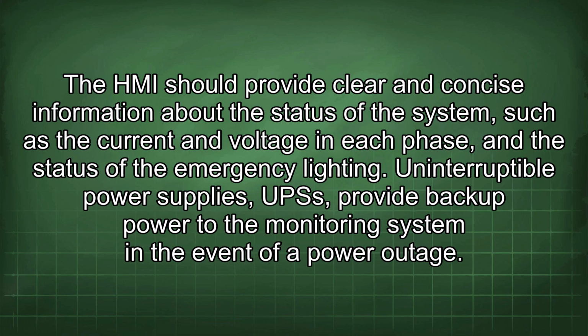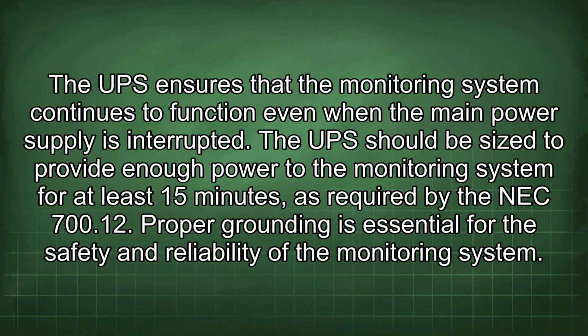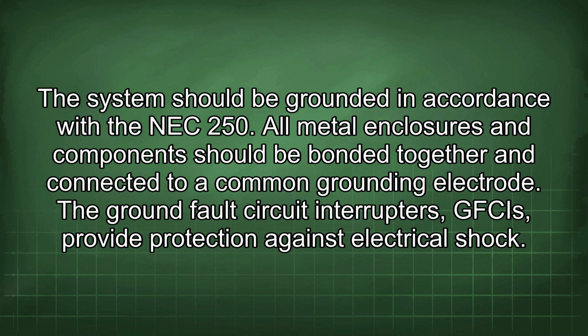Uninterruptible power supplies, UPSs, provide backup power to the monitoring system in the event of a power outage. The UPS ensures that the monitoring system continues to function even when the main power supply is interrupted. The UPS should be sized to provide enough power to the monitoring system for at least 15 minutes as required by the NEC 700.12. Proper grounding is essential for the safety and reliability of the monitoring system. The system should be grounded in accordance with the NEC 250. All metal enclosures and components should be bonded together and connected to a common grounding electrode.